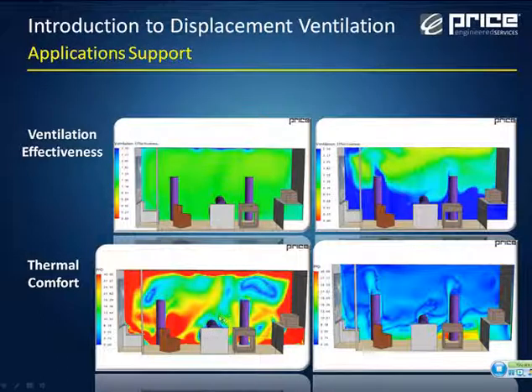The zone around the person in the bed is still only around 10 to 15, which is not bad. But if you look at all the visitors, it's not a terribly comfortable environment. You're still seeing high velocities. And ASHRAE 55 says you should design a room to maintain 20% PPD, so maintaining 80% of people satisfied in this room. And this room would not fit the bill.